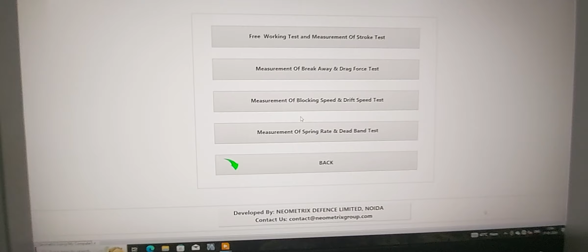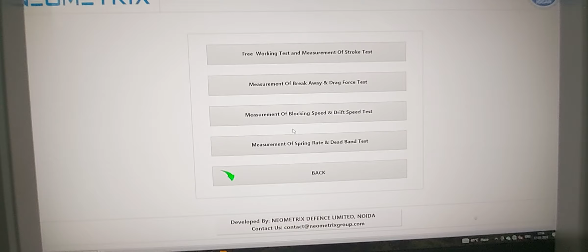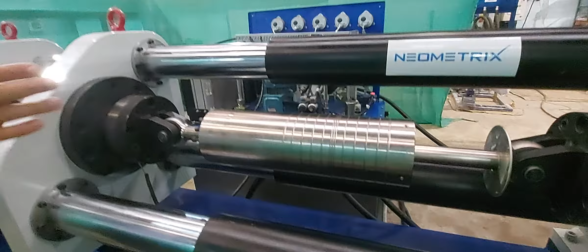So when we do a manual test, these are the tests that are available, free operability test. And so as I discussed, snubbers can be tested for any velocity, any acceleration. It can test lock velocity, it can test lock acceleration, it can test cyclic loading, it can do free operability test, it can measure the friction load or drag force. So this test bench can test 100% everything of any snubber. You can test here up to 25 ton, and we will just show you the free operability test. So we select the free operability test.